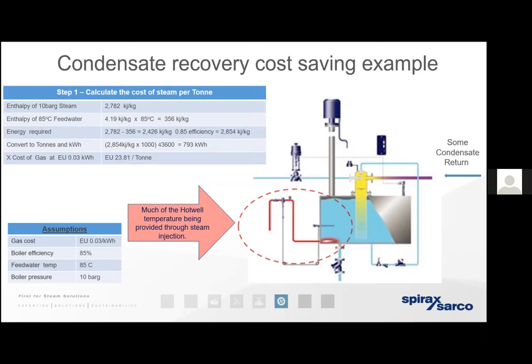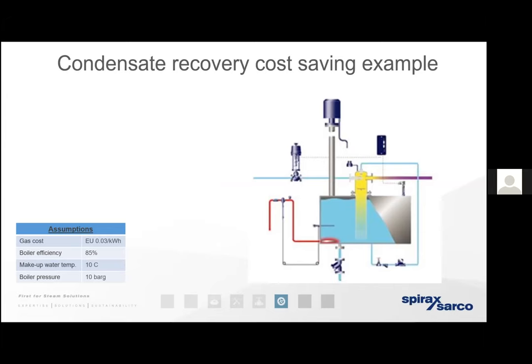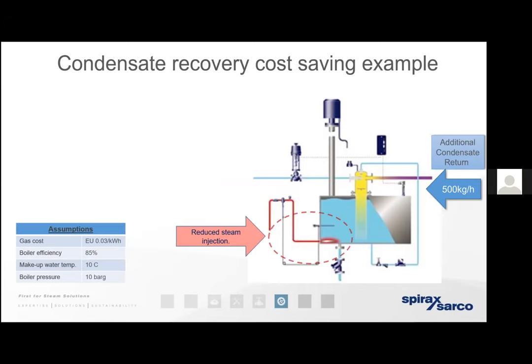Just a quick energy cost-saving example: let's say gas costs 3 cents per kilowatt hour, boiler efficiency is 85%, operational pressure is 10 bar gauge, and the hot well temperature gauge reads 85 degrees. We might mistakenly believe the hot well temperature is maintained through excellent condensate recovery, when in fact it could be held at that temperature through direct steam injection — taking steam from the boiler and adding it to the hot well while condensate is being lost through open-failed steam traps or going to waste needlessly. Recovering an additional 500 kilograms per hour of condensate reduces both the condensate deficit and the direct steam injection requirement.